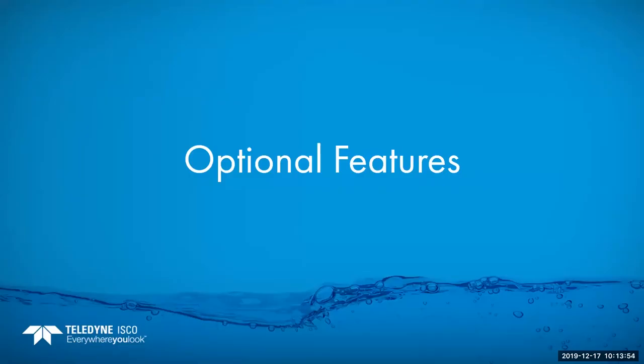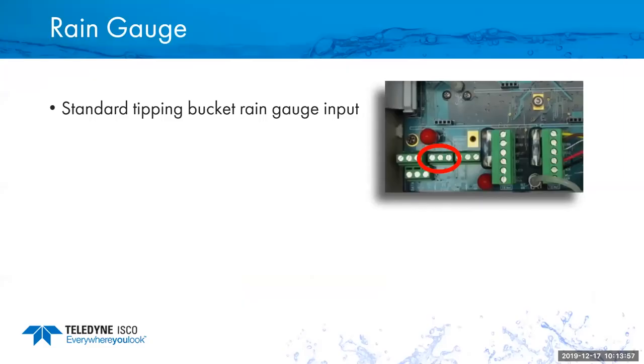Some of the optional features of the signature meter is the ability to bring in a rain gauge. We can do the rain gauge, like our 674 rain gauge, which uses a reed switch closure. So whenever the bucket tips, we would see that as maybe 1/100th of an inch of rain. We can store that in the signature meter, and we can also use that to create events to enable a sampler, something like that, based off of a parameter that you've set in the flow meter of the signature.